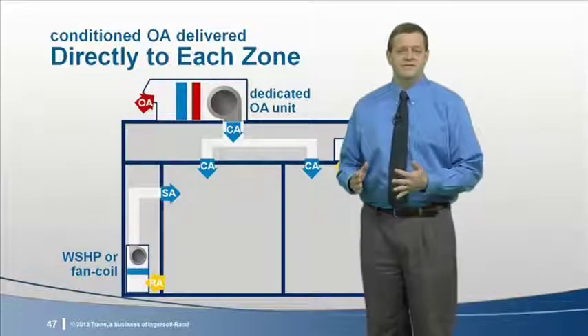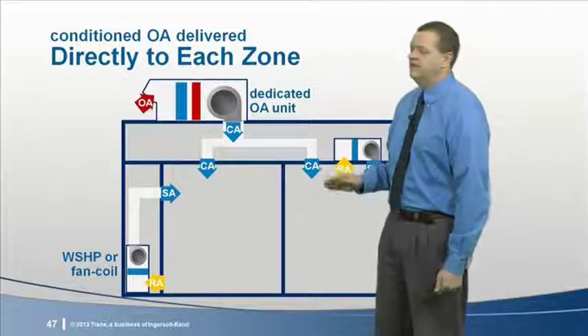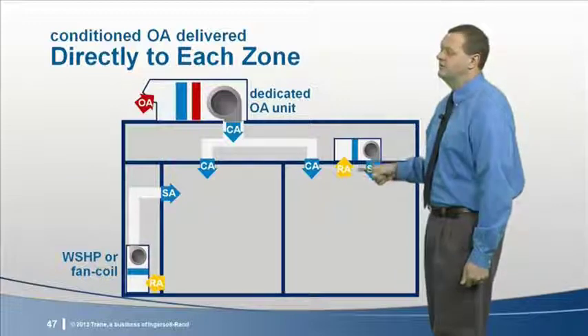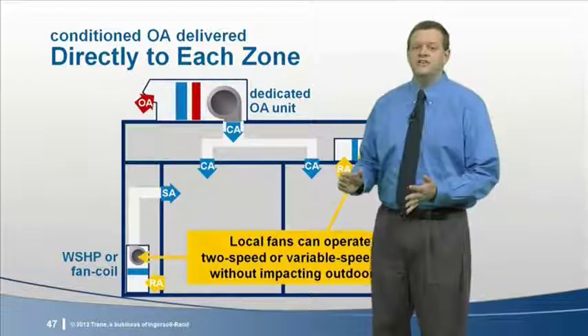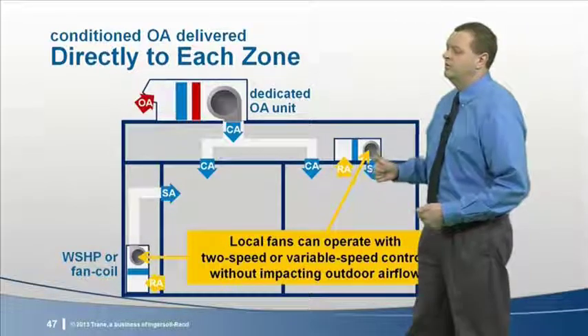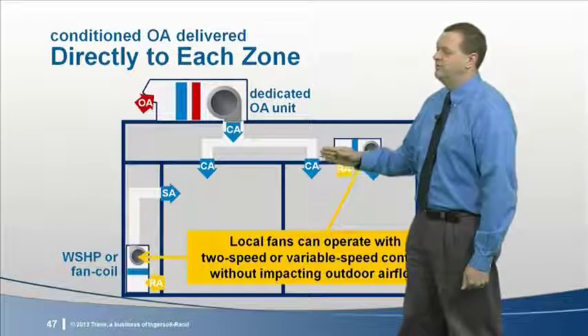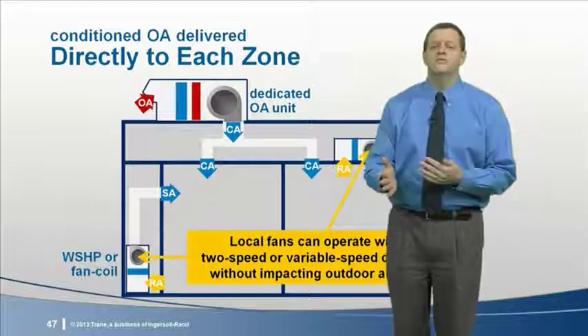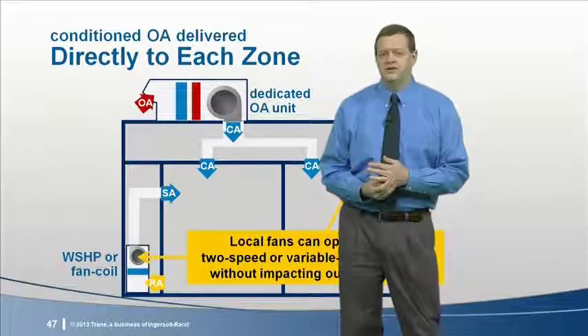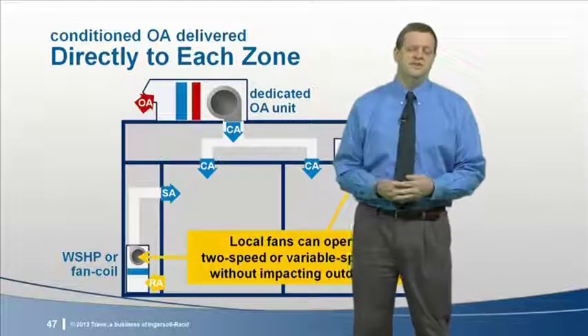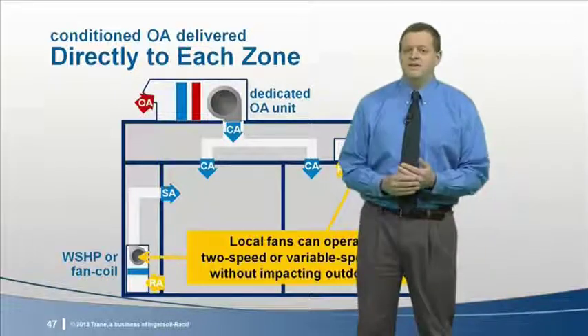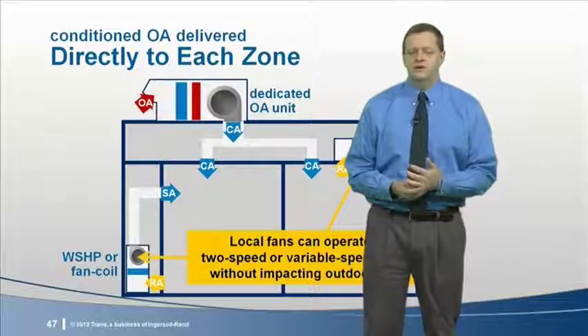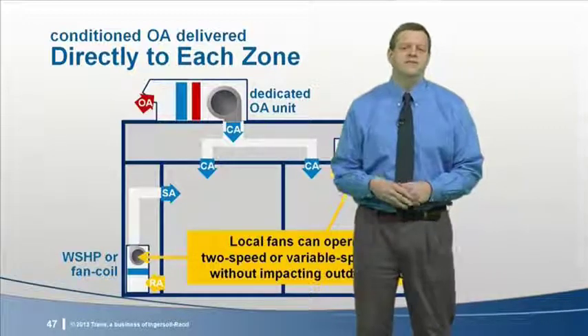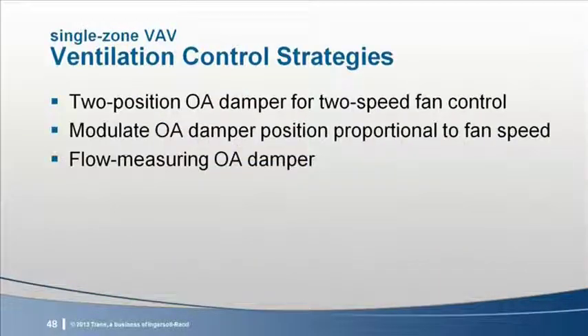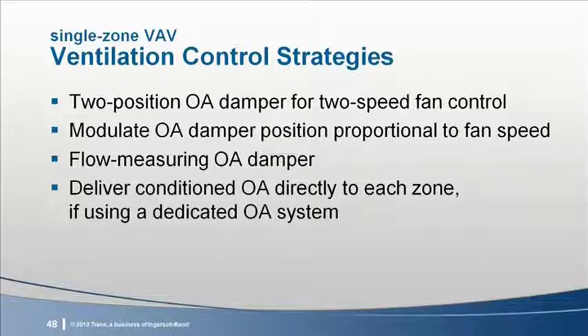Now a better choice would be to deliver the conditioned outdoor air directly to each zone. In this case, the local heat pump or fan coil conditions only recirculated air. Since outdoor air is not distributed through the local fan, that fan can operate with a 2-speed or a variable speed motor without impacting how much outdoor air is delivered. This direct-to-zone approach also affords the opportunity to deliver this outdoor air at a cold temperature, rather than reheated to neutral. This has several installed cost and energy-saving benefits. I discussed these benefits in detail during a 2012 E&L program on water source heat pump systems. It's listed in your bibliography if you want to learn more. So when a dedicated outdoor air system is used, consider delivering the conditioned outdoor air directly to each zone, rather than to the inlet of the fan coils or heat pumps.